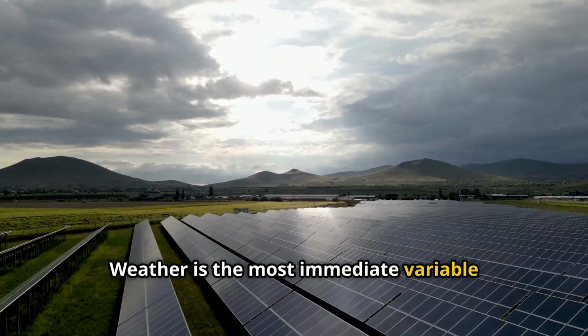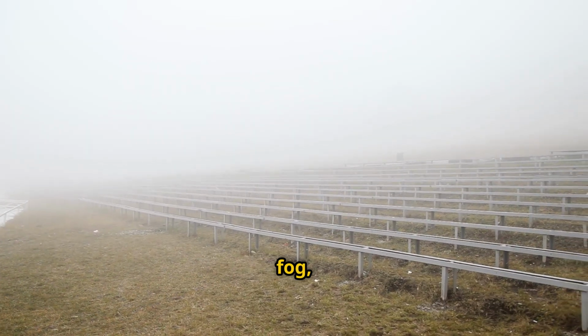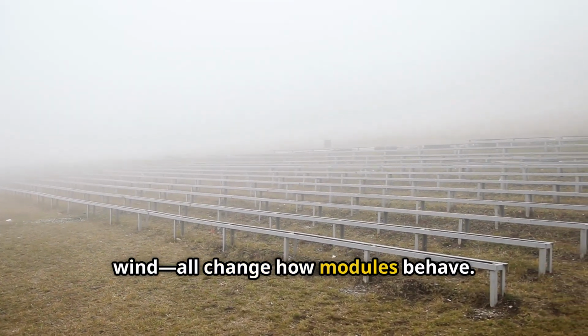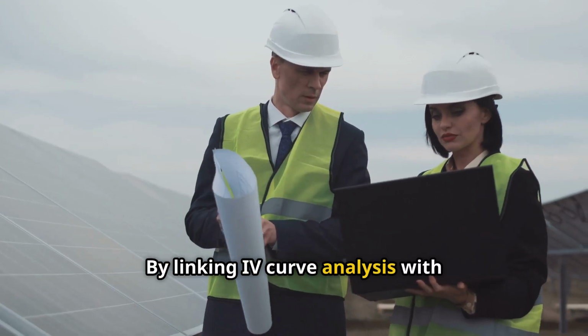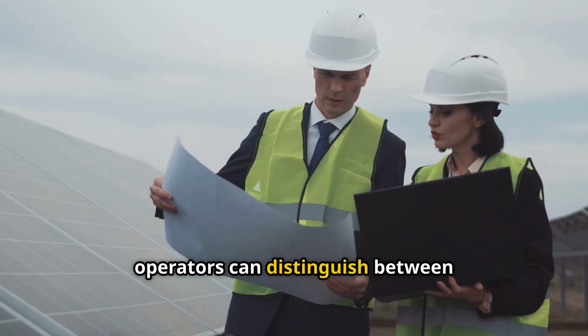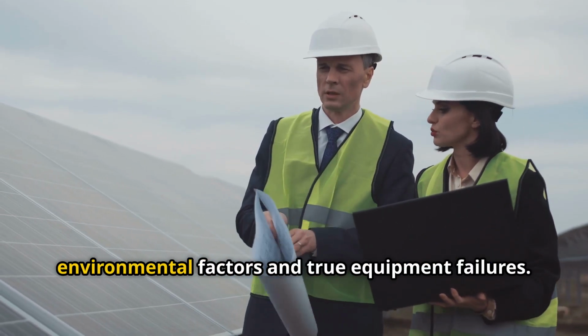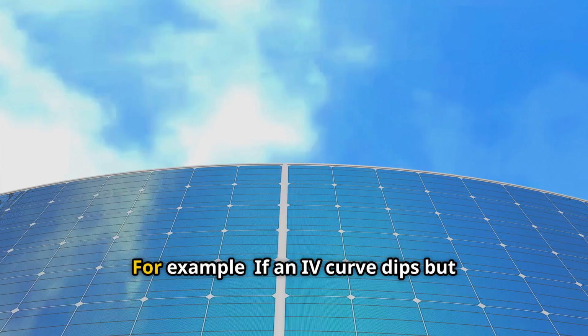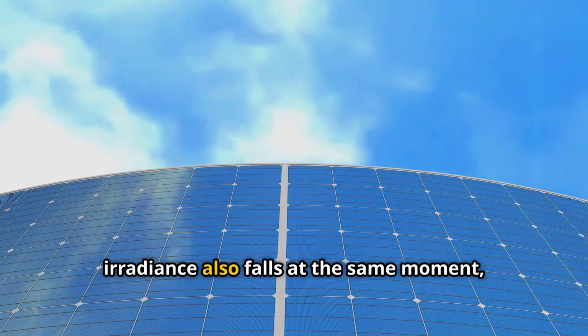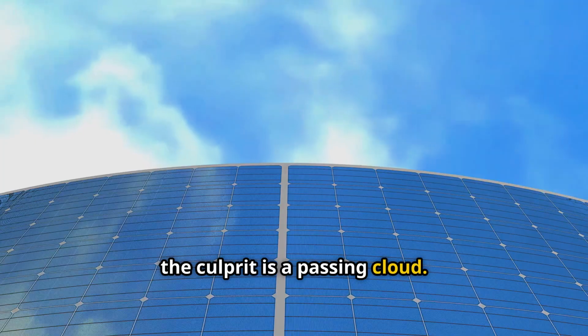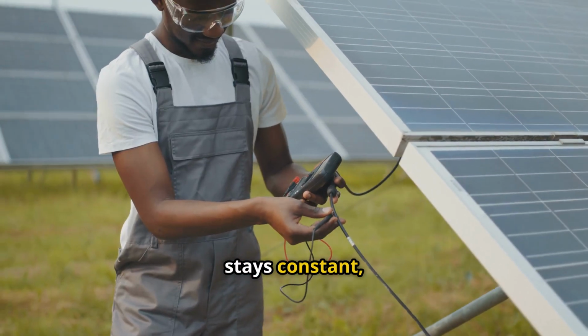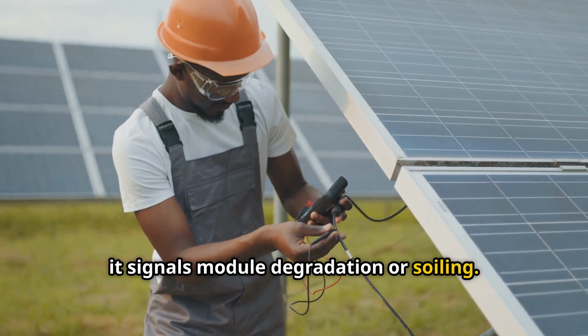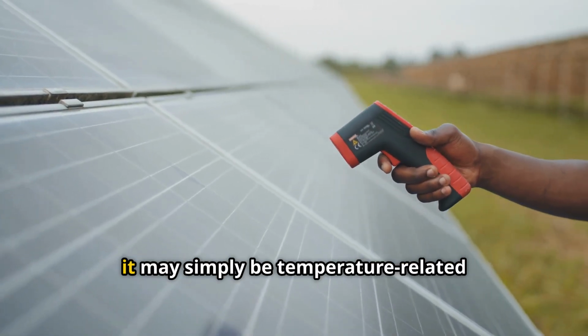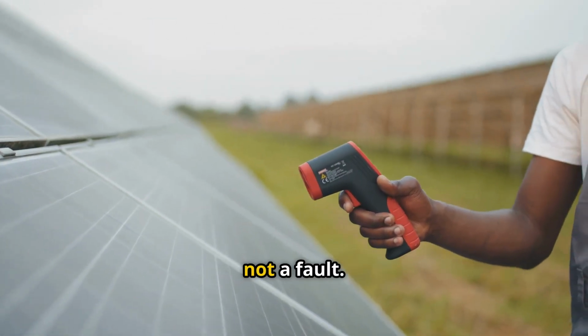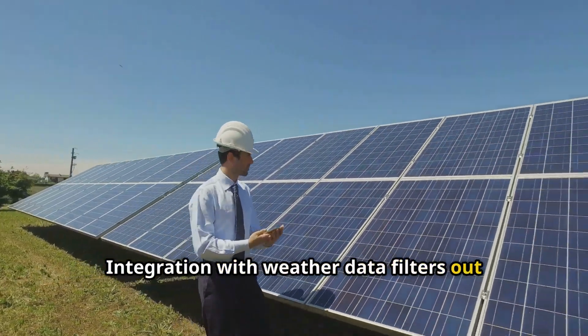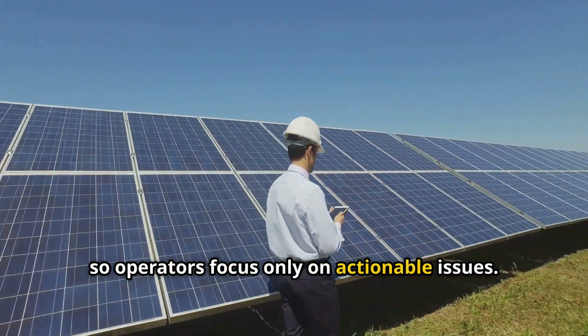Weather is the most immediate variable impacting solar performance. Clouds, fog, dust, humidity, wind all change how modules behave. By linking IV curve analysis with real-time weather feeds, operators can distinguish between performance drops caused by temporary environmental factors and true equipment failures. For example, if an IV curve dips but irradiance also falls at the same moment, the culprit is a passing cloud. If current declines while irradiance stays constant, it signals module degradation or soiling. If VOC decreases during hot afternoons, it may simply be temperature-related voltage suppression, not a fault. Integration with weather data filters out the noise, so operators focus only on actionable issues.